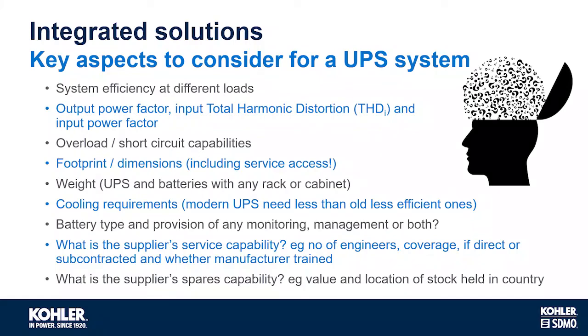And then we look at the supply. This is what affects the mains or the generator. So we need to make sure that the input total harmonic distortion on the current is understood, and what that power factor will be at the load, which is on the generator or mains. Understanding the overload and short circuit capabilities of the UPS is very important, especially depending on the types of load. So that needs to be a consideration.